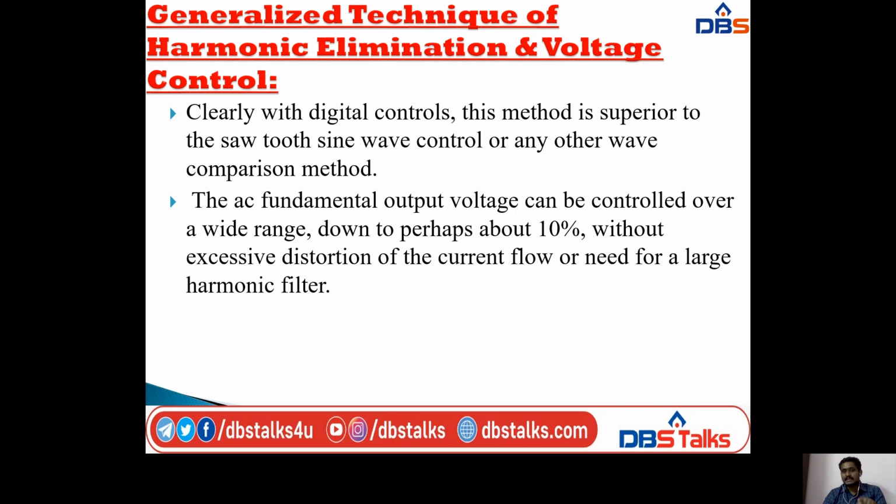The AC fundamental output voltage can be controlled over a wide range, down to perhaps about 10%, without excessive distortion of the current flow or need for a large harmonic filter.